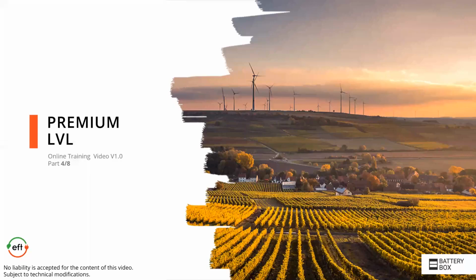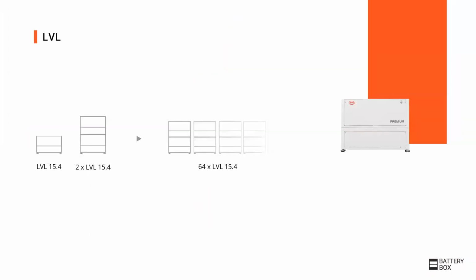The next premium product we will look at is the Battery Box Premium LVL. Unlike the HVS and HVM, the LVL is a low voltage battery with about 50 volt. One LVL consists of 15.4 kilowatt hours, and up to 64 LVL can be put in parallel to achieve a maximum capacity of 984 kilowatt hours, so nearly 1 megawatt hour in a single system. Up to 2 LVL can be stacked to save space.